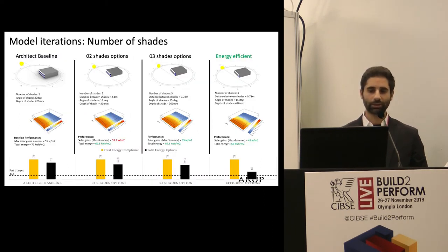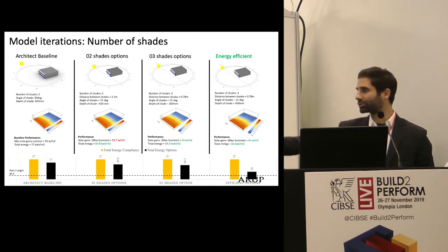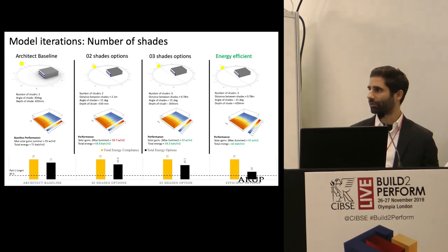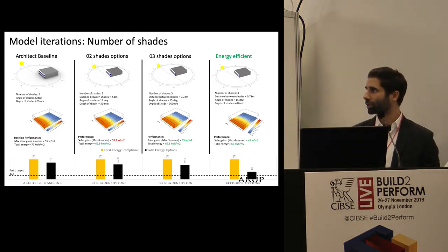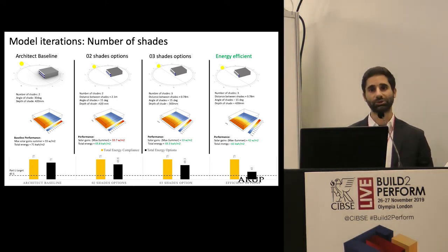Next slide is us taking the architect through the options. They wanted 100% glazing, and we were trying to show them that no matter what we did, we could never pass the compliance. You can see that at the bottom of the page. So that was varying and looking at all the variables, all the different options. We could not pass the compliance by 30%.